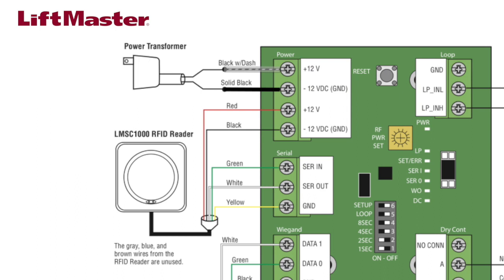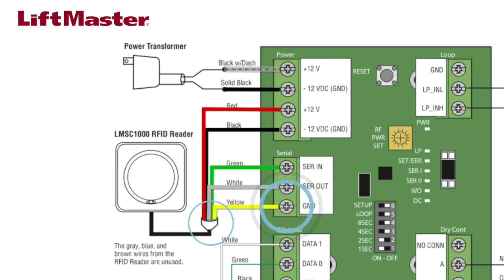To supply power to the reader, connect the black wire from the reader to the negative 12-volt DC terminal on the Wiegand interface board. Connect the red wire to the positive 12-volt DC terminal on the interface board. To wire reader data to the Wiegand interface, connect the green wire from the reader to the serial in terminal on the Wiegand interface board. Connect the white wire to the serial out terminal on the interface board. Connect the yellow wire to the ground terminal on the interface board.